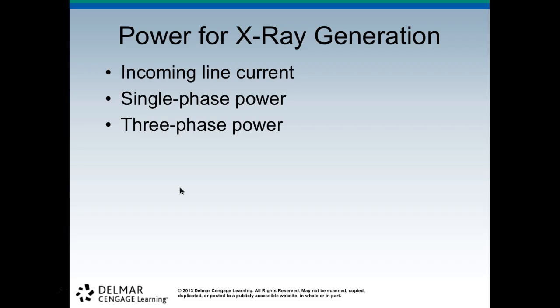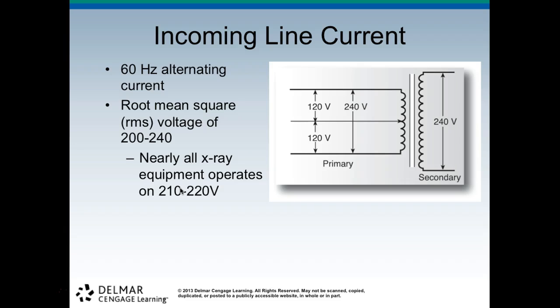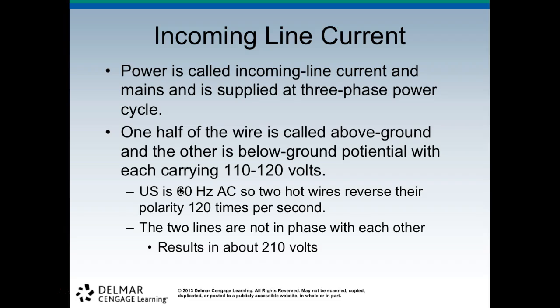So, power for X-ray generators. The incoming line current, single-phase power and three-phase power. We're going to talk about that a little bit. So incoming line current is 60 hertz alternating current, so AC, right? The root mean square, the RMS voltage, is between 200 and 240. Nearly all X-ray equipment is 210 to 220. It's typically 110 coming in, and we double it, so we have 220. All right, power is called incoming line current, or mains, and is supplied at three-phase power cycles. So we're going to talk about that.